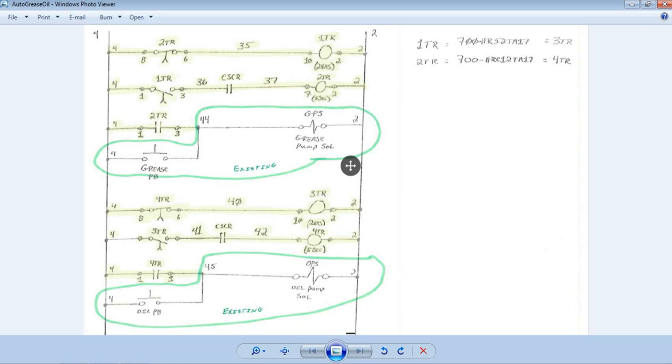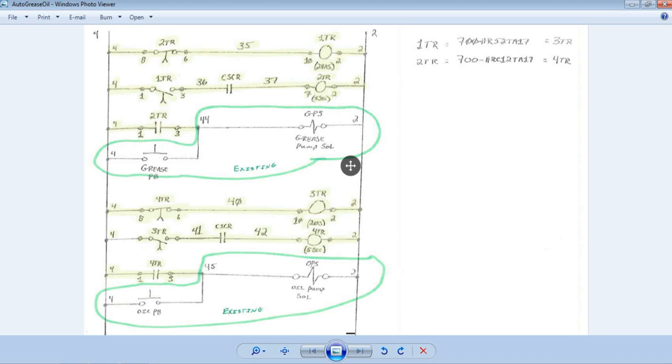I have to add four relays, like real relays. I have to wire between the CSCR, which is the cycle start control relay. I have to have two more contacts off it. So if I didn't have two more contacts, I would have to add another physical relay to get some more contacts. I happen to have seven and eight contact pairs on this thing, so I'm very lucky that I actually have them. And then I have to buy the right relays that have normally closed contacts, normally open contacts, and instantaneous contacts. This is the timer timing, this is the not done, this is the done, and this is the timer timing in the timer instruction in Bradley.